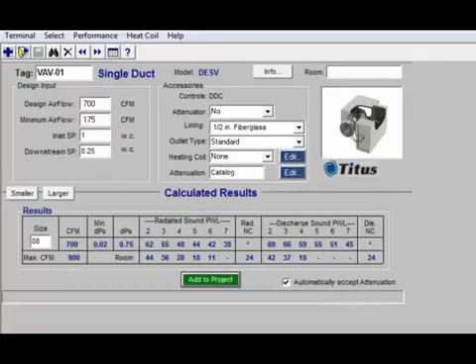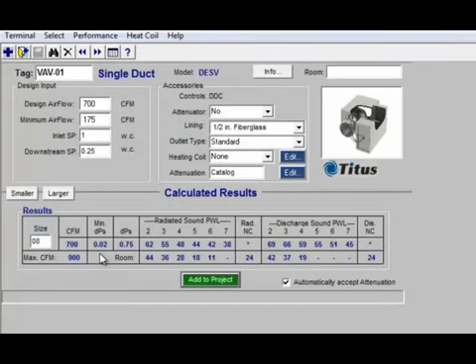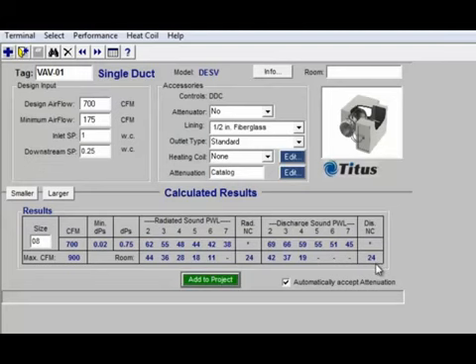Here's our result. You can see that it's giving us an 8-inch inlet duct for 700 CFM. That follows my rule for trying to keep the maximum inlet velocity as close to 2,000 feet per minute as possible. The minimum pressure requirement is 0.02 inches — that's the kind of low pressure requirement you get with a basic single duct assembly because of the static pressure regain inside the cabinet. The program also gives us our radiated sound power levels and discharge sound power levels, as well as room sound pressure levels and the calculated radiated noise criteria (NC) level — NC 24 for radiated sound and NC 24 for discharge sound.